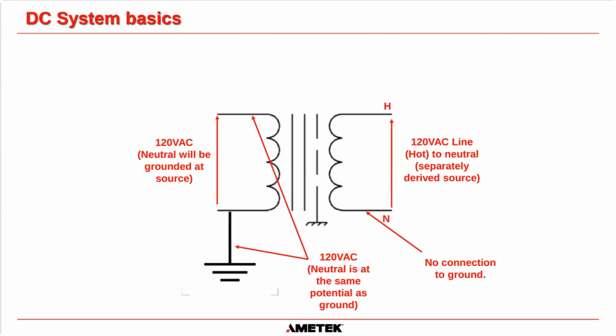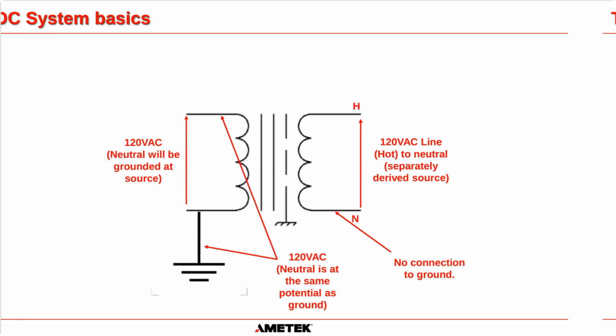Okay. So for ease, because we're in America, I know there are other people from the Middle East and Europe on this webinar, but we're going to stick with 120 volts as the AC input. Okay, the neutral will be grounded at the source. So if I measure between hot and neutral, I'll get 120 volts. And if I measure between hot and ground, I'll get 120 volts on the primary. But if I create a secondary here and it's just a one-to-one ratio, between hot and neutral, yes, I'm going to have 120 volts AC. And it's classed as a separately derived source. There is no connection to ground. This is as if we're creating a new source of power altogether. And that's why it's called a separately derived source. And hopefully the next few slides will help explain that a little bit more.